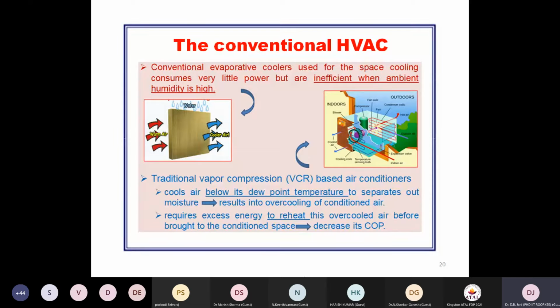So this is the limitation: sometimes in the process of removing the humidity, overcooled air will be there, with a supply temperature maybe around 5 to 7 degrees. That is very low for the application. In that case, you might have to provide reheating to raise its temperature to around 17 to 18 degrees centigrade. At that time, you have to expend more energy in the form of a heater, and ultimately that will disturb the COP by reducing it to a lower value.